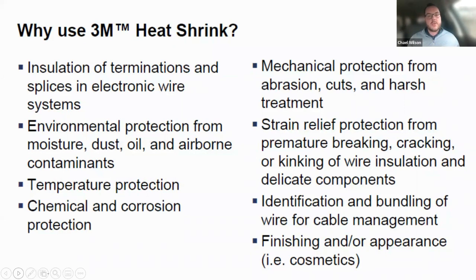It's nice because you can cut it up. You can get a 48-inch tube, cut it up into the sizes you need it. You can get a 100-foot spool if you're working on a job. Really easy to use. Everybody's pretty familiar with it. It's an economic option if you don't need the performance as much as what you would use for cold shrink. So those are some of the advantages, but it still provides that insulation, the environmental protection, temperature protection, chemical and corrosion protection, all that kind of good stuff.